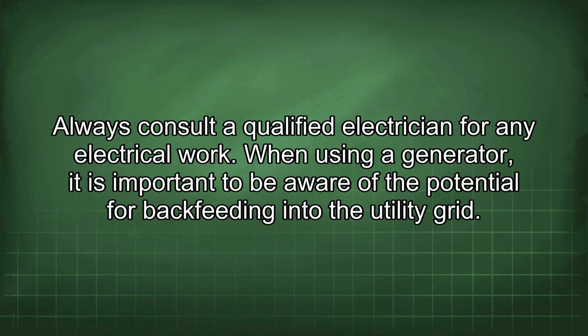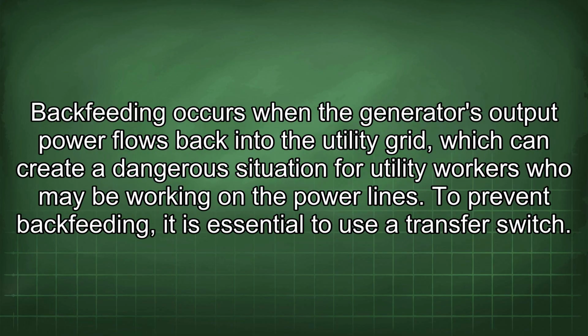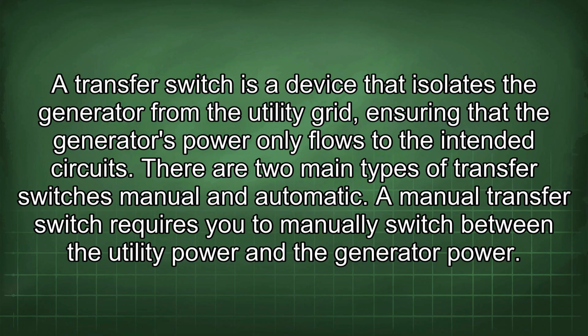When using a generator, it is important to be aware of the potential for backfeeding into the utility grid. Backfeeding occurs when the generator's output power flows back into the utility grid, which can create a dangerous situation for utility workers who may be working on the power lines. To prevent backfeeding, it is essential to use a transfer switch. A transfer switch is a device that isolates the generator from the utility grid, ensuring that the generator's power only flows to the intended circuits.